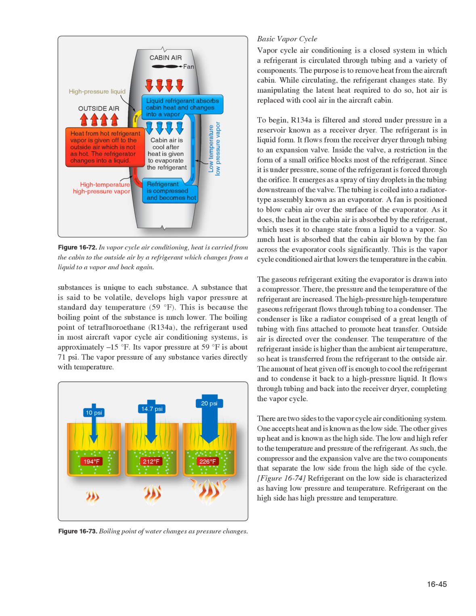The high-pressure, high-temperature gaseous refrigerant flows through tubing to a condenser. The condenser is like a radiator comprised of a great length of tubing with fins attached to promote heat transfer. Outside air is directed over the condenser. The temperature of the refrigerant inside is higher than the ambient air temperature, so heat is transferred from the refrigerant to the outside air. The amount of heat given off is enough to cool the refrigerant and to condense it back to a high-pressure liquid. It flows through tubing and back into the receiver dryer, completing the vapor cycle.